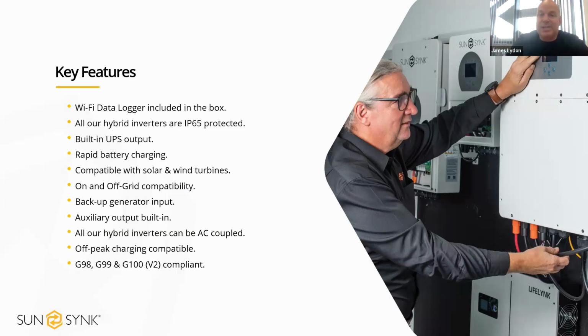With the backup generator connected, you can set on the inverter, right, once the battery gets to 30% SOC, our inverter can send the signal to the generator, if the generator supports it with the ATS, to turn on. The generator kicks in, and when the generator power comes into our inverter, it essentially splits two ways. It'll go one way to power the load and the other way to charge the battery at the same time. So, if someone has previously been off grid and running off a backup generator, that generator is on all the time they need power.